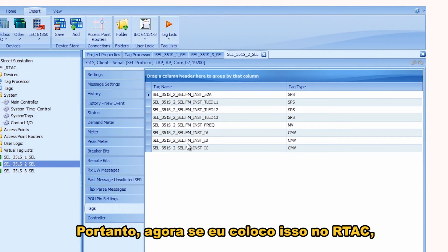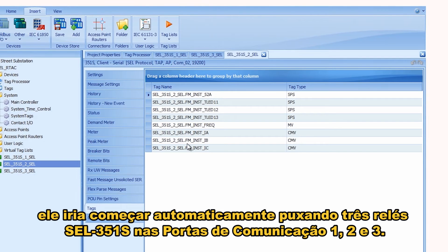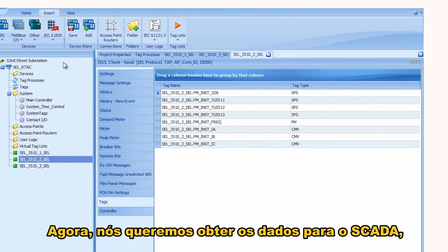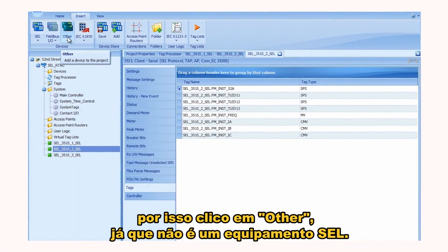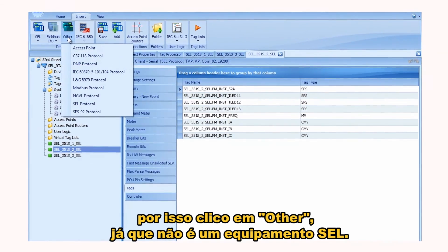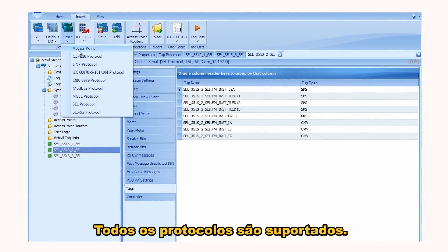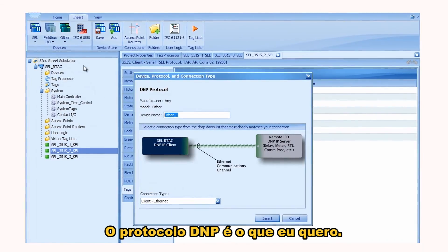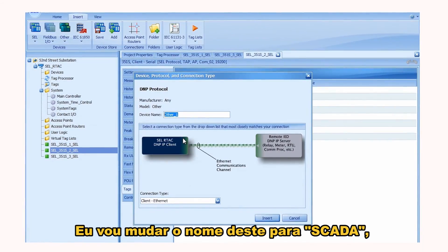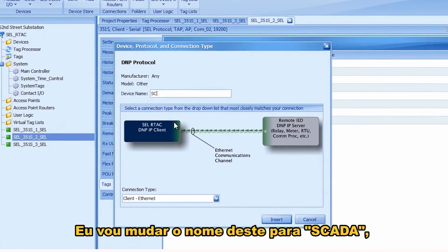If I loaded this into the RTAC, it would automatically start pulling three SEL 351Ss on COM ports 1, 2, and 3. Now we want to get that data over to SCADA. I'll click on 'Other' because it's not an SEL device, and you can see all the protocols supported there. DNP protocol is the one I want. I'll change the name of this device to 'SCADA'.